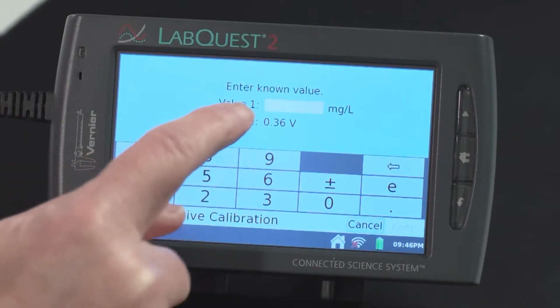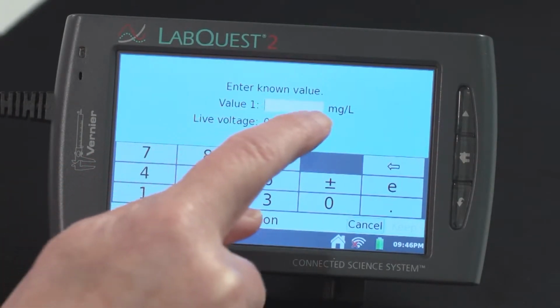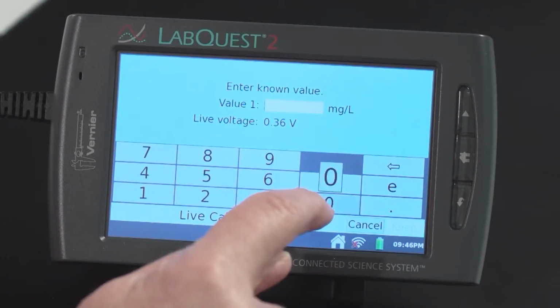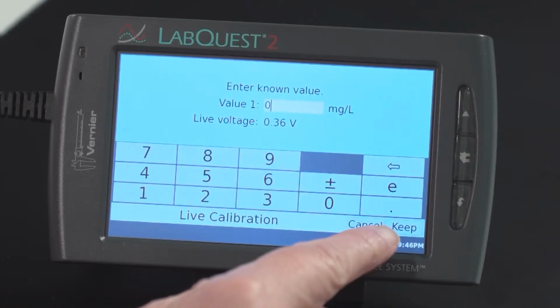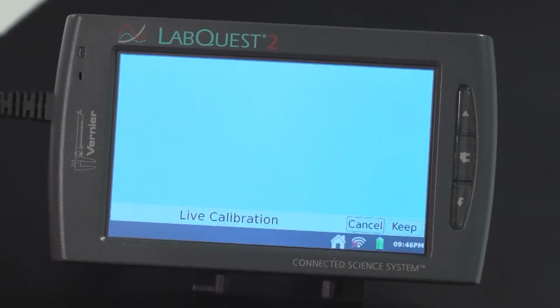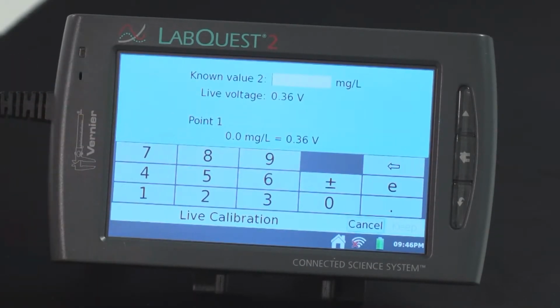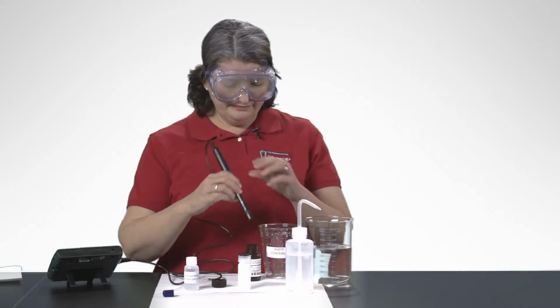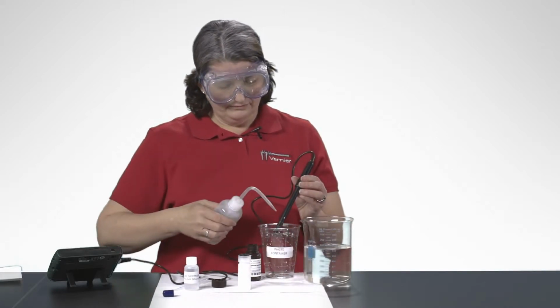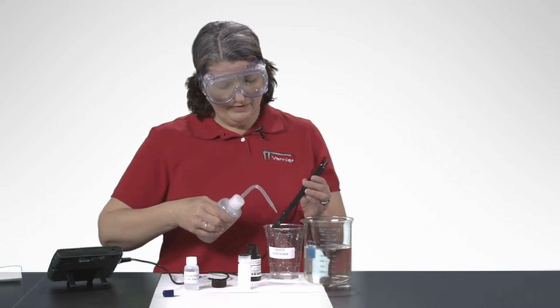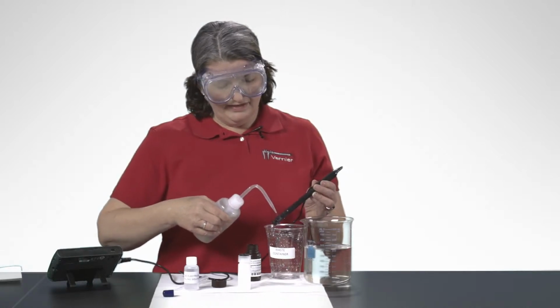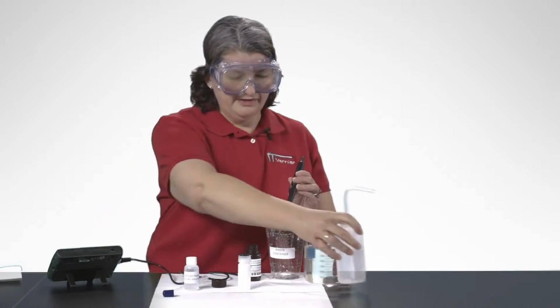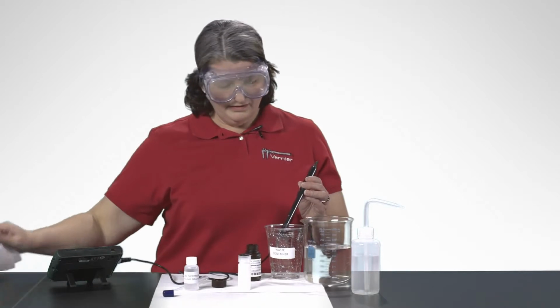Okay, so we're stable here. So for value number 1, this is our 0 milligrams per liter. So I just type a 0 and say keep. And now it's asking me for my known value number 2. So let me rinse this off. Need to rinse this very well. You don't want any of that sodium sulfite solution still on there. Dry it.